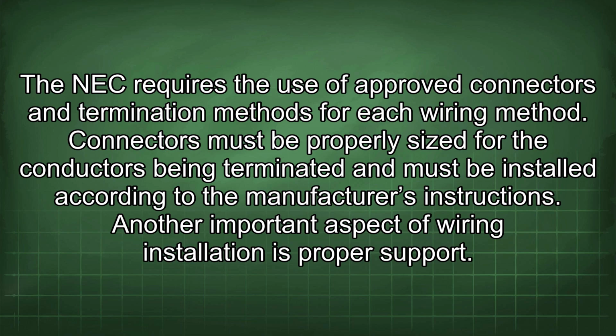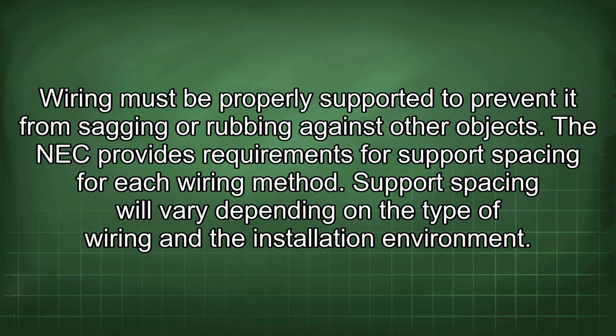Another important aspect of wiring installation is proper support. Wiring must be properly supported to prevent it from sagging or rubbing against other objects. The NEC provides requirements for support spacing for each wiring method. Support spacing will vary depending on the type of wiring and the installation environment.